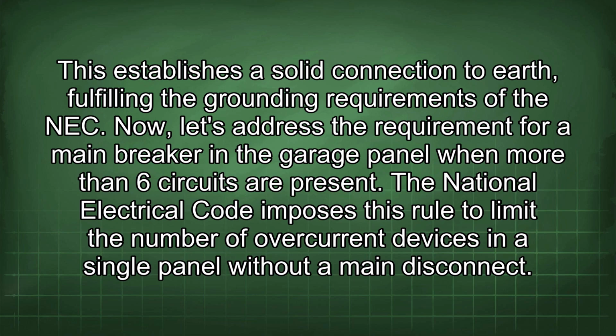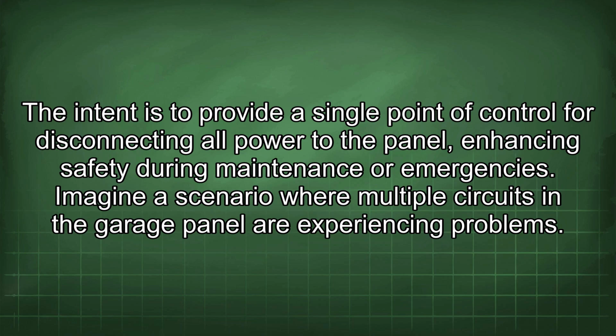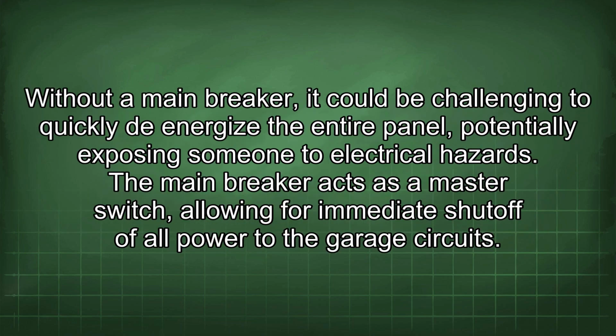Now let's address the requirement for a main breaker in the garage panel when more than 6 circuits are present. The National Electrical Code imposes this rule to limit the number of overcurrent devices in a single panel without a main disconnect. The intent is to provide a single point of control for disconnecting all power to the panel, enhancing safety during maintenance or emergencies. Imagine a scenario where multiple circuits in the garage panel are experiencing problems. Without a main breaker, it could be challenging to quickly de-energize the entire panel, potentially exposing someone to electrical hazards. The main breaker acts as a master switch, allowing for immediate shut-off of all power to the garage circuits.